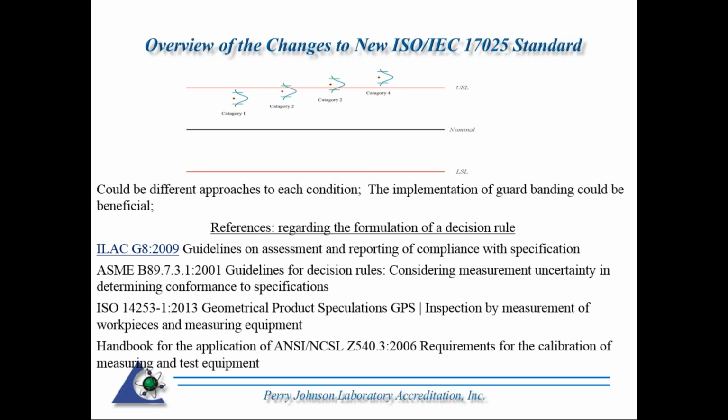The dot in the middle there indicates a value. The two lines below and above each dot indicate the measurement uncertainty. Hence, that's a gray area there. You have a value, and then you have that gray area of uncertainty. So, for example, category 1, that red line, USL, means upper standard limits or tolerance or whatever you want to refer to. When you're stating pass or fail, that is the limit that we're looking for our calibration point not to exceed.